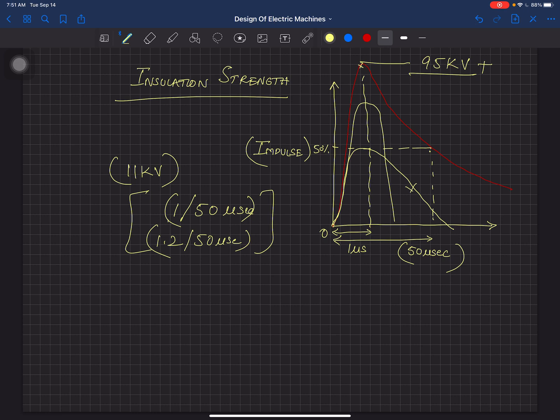These two are flashovers. So this is also a transformer testing which is normally done for any of the transformers for 11 kV, and certainly for every 11 kV transformer that is built, you have to get it tested from some laboratory in our high voltage lab. We have this facility of testing that transformer over here, and you have to get a certificate for that.